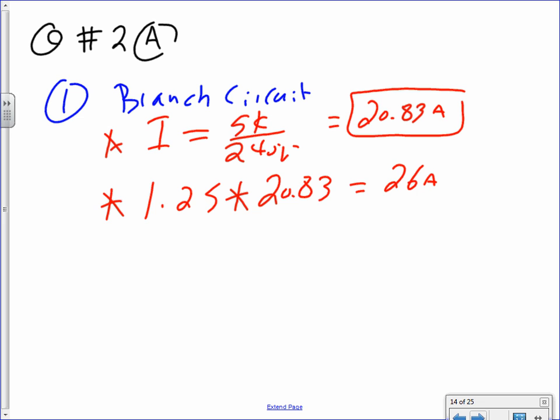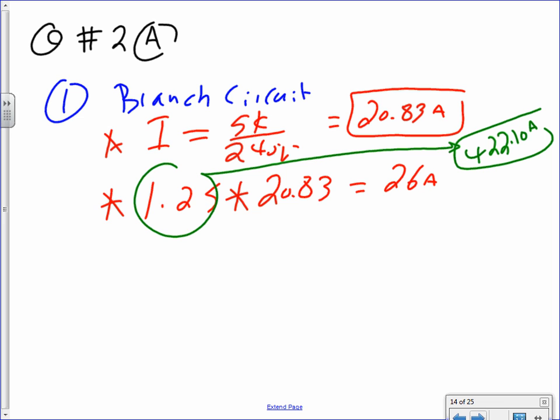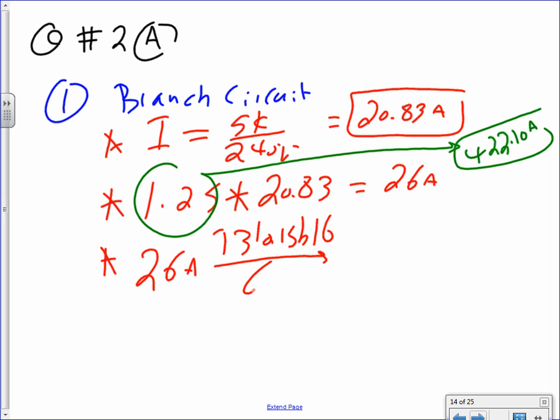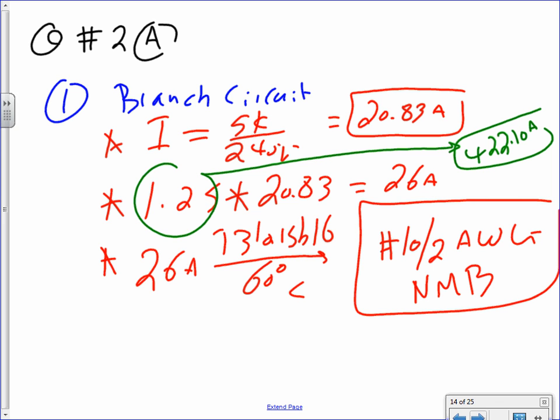Okay, and this is coming from 422.10(A). It's a continuous load. That's your reference for this number. Okay, then the rest is history, guys. We're going to go size. I have 26 amps. I need to go to Table 310.15(B)(16) under the 60-degree column because it's Romex, and that will get you number 10 AWG NM-B cable.